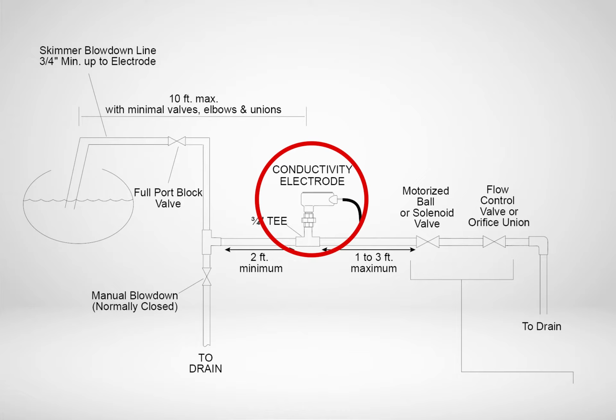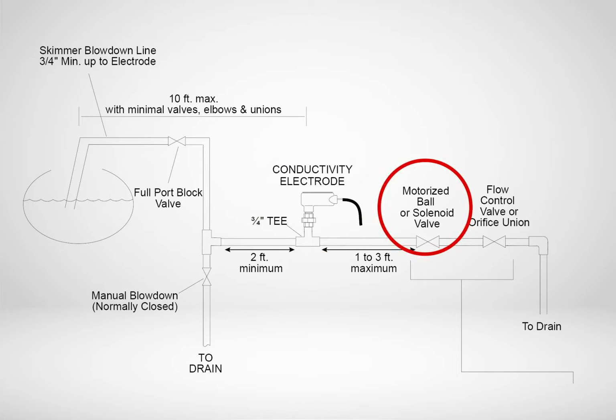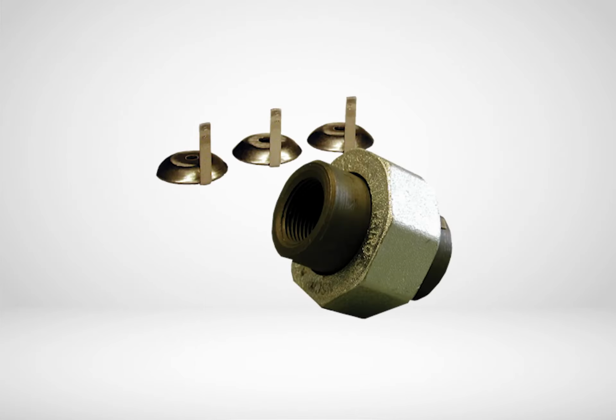To determine if the flashing is an issue, simply close a valve downstream from the sensor and look to see if the readings increase. To minimize flashing, downstream of the valve should have either a throttling valve or an orifice union installed to maintain back pressure at the sensor.